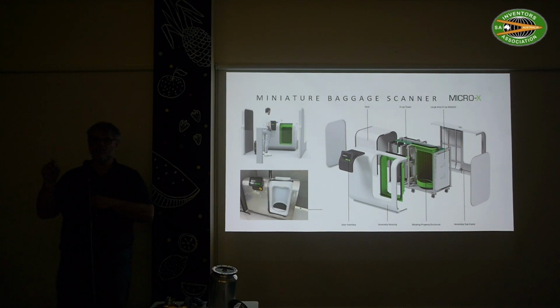Part of the big problem is that all these little shields that you have are all lead lined, and there's a thing in X-ray equipment called labyrinthing, which means if you have two slides like this, it doesn't work. You actually need a corner here and a corner here to allow the X-ray to bounce around as much as you can. So doors will have to slide into your V shape and things like that. There's a whole bunch of trickery going on to make sure that we don't expose any X-rays to the outside. So not easy. We're still expecting quite a bit of issues by the time we're putting this together.